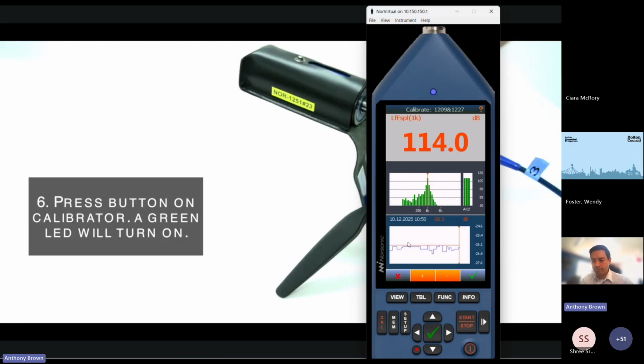You will get a little bit of drift throughout the year with the temperature. But as long as it's not drifting from, I don't know, 25 to 28. So you did it at the start and it was 25, and then you did it after and it started reading 26, 27, 28. You know, if it's gone more than a dB, then there is a bit of concern whether the cable's got damaged or the microphone's got damaged.